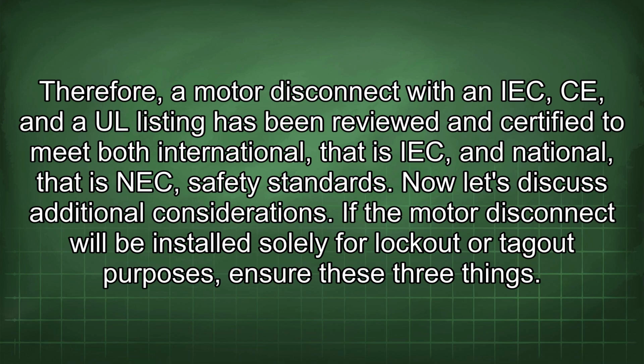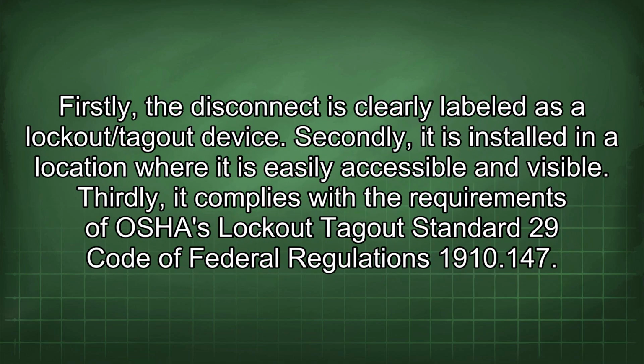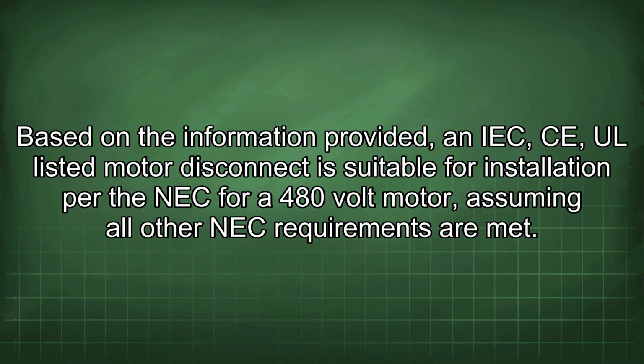Now let's discuss additional considerations. If the motor disconnect will be installed solely for lockout or tagout purposes, ensure these three things. Firstly, the disconnect is clearly labeled as a lockout/tagout device. Secondly, it is installed in a location where it is easily accessible and visible. Thirdly, it complies with the requirements of OSHA's Lockout/Tagout Standard 29 Code of Federal Regulations 1910.147. Based on the information provided, an IEC, CE, UL listed motor disconnect is suitable for installation per the NEC for a 480-volt motor, assuming all other NEC requirements are met.